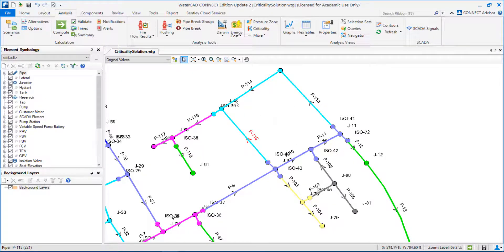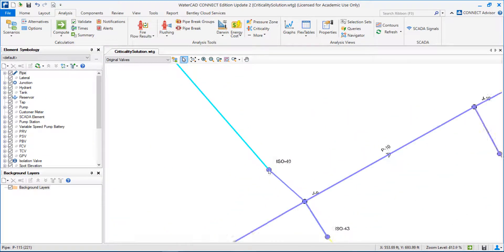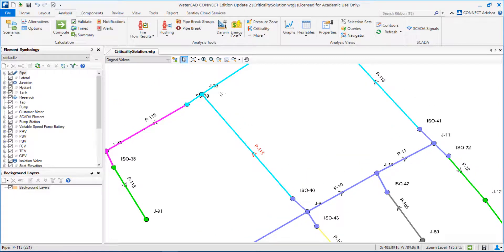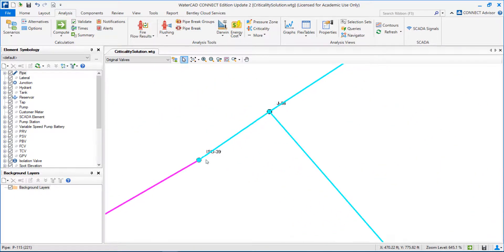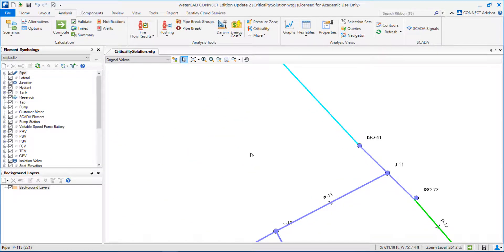This is a segment because if I have a burst here, or here, or here, I'm only able to isolate all this segment — I cannot isolate just this pipe, or this pipe, or this pipe. I have to close all these pipes. Why? Because I only have valves here, the isolation valve here, another isolation valve here, and another isolation valve here.